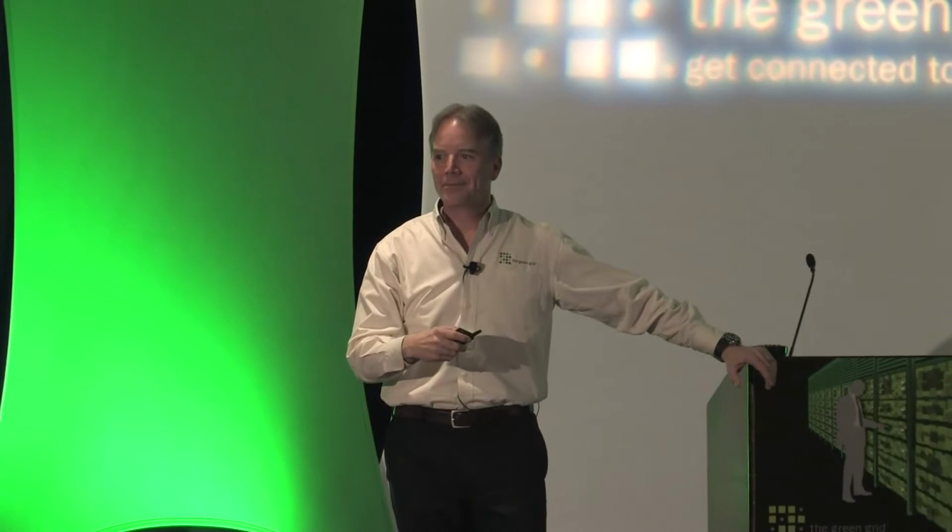What are we doing in data centers? We want to get the maximum performance out of the equipment. I'd like to use the smallest amount of equipment to do that as possible. We start to hit the ceiling of air. There is a ceiling, and we found it's 28 kilowatts with a certain amount of area in a container. Okay? 28 per cabinet. All right, the next one is free cooling everywhere.